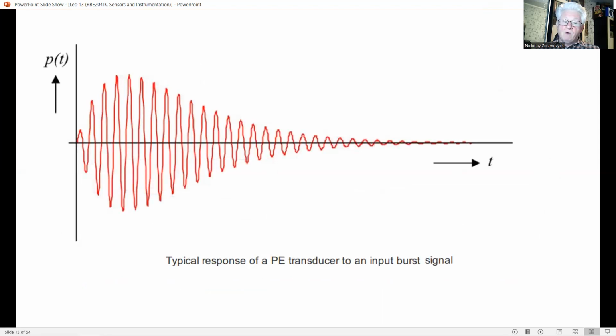The response of a piezoelectric transducer to a burst signal shows a rather large rise time due to the high quality factor of this transducer type. Actually, this effect occurs twice, first at the transmitter and the second time at the receiver. The starting point of the echo is easily obscured by noise.